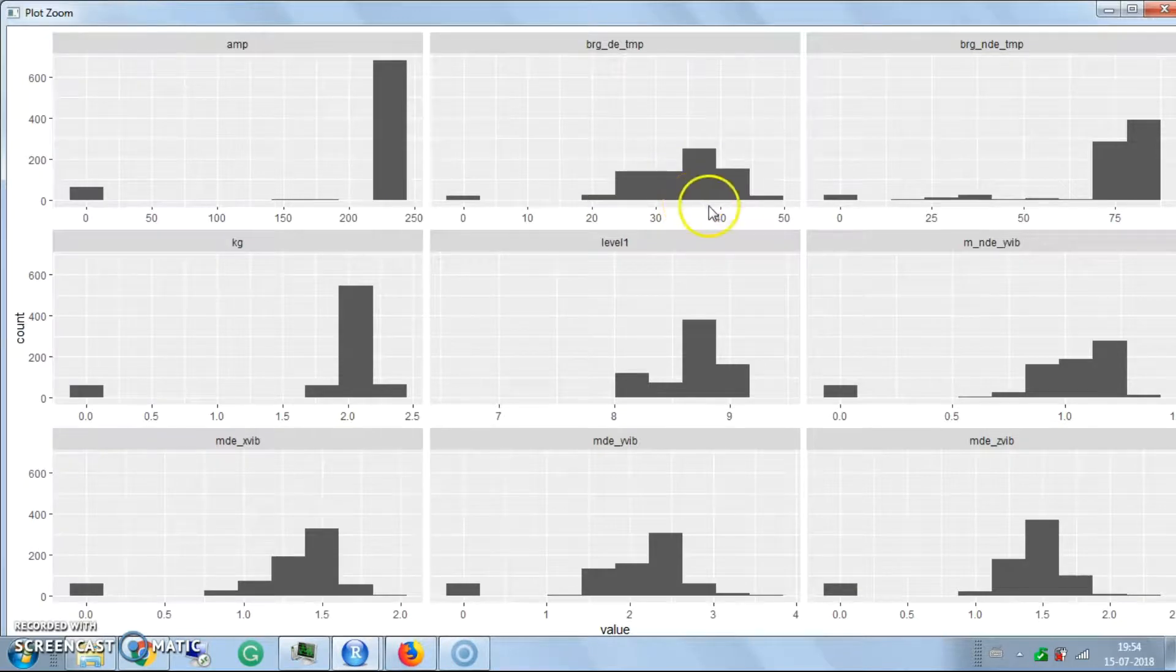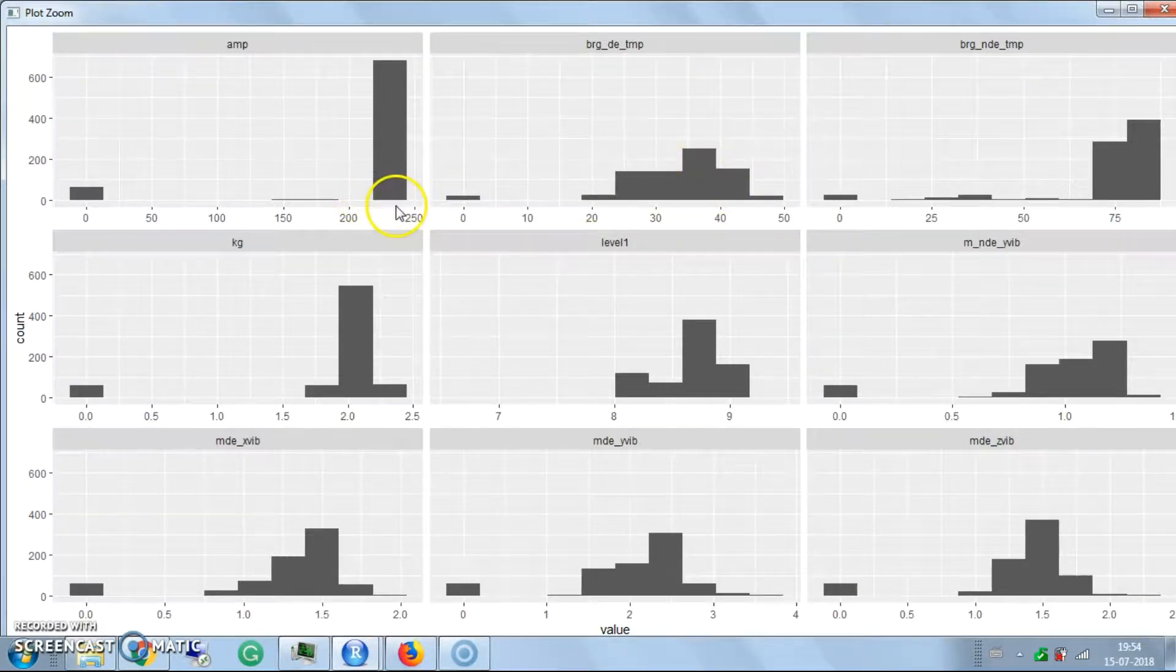The histogram shows the maximum variations and maximum counts. This is the bearing temperature - it generally ranges between 35 to 40. The maximum count shows the ampere, which runs at 235 ampere. These histograms interpret a lot of information about the data.